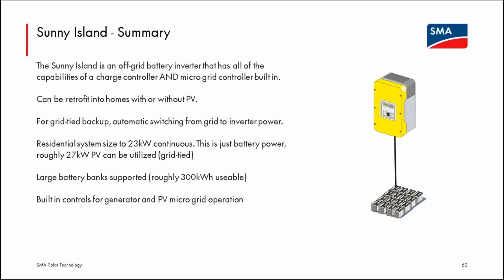Okay, the next question is, do you need the RS485 cable between the Sunny Boys 6 and the Sunny Island to share AC coupling communications? So no, for the AC coupling, what we used to have is that with the Sunny Boys, you would wire RS485 communications to dynamically change Sunny Boys from grid tied mode to, in essence, off-grid mode when the Sunny Island sensed a loss of grid. Our Sunny Boys now do not have the capability of being wired up for RS485 communications.